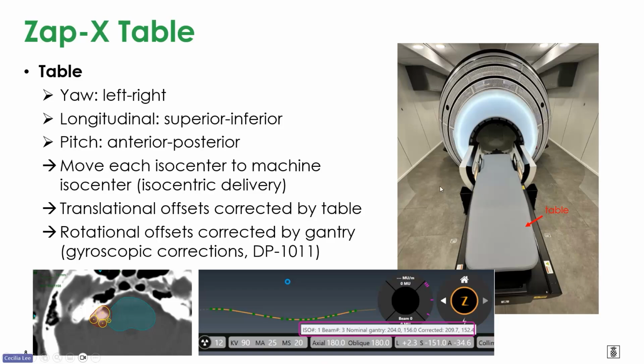So after IGRT, you get some translational offset that is corrected by the table, and then the rotational offset is corrected by gantry angle. It's called the gyroscopic correction. So you can see you have a nominal gantry angle, like the axial and oblique angle, and then you can see the corrected angle after IGRT is performed. It's only available in DP 1011 or above.